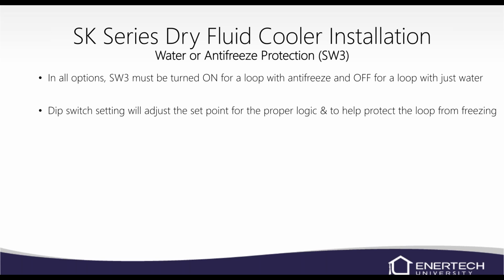Water antifreeze protection, which is switch number 3 on the dip switches. In all options, switch number 3 must be turned on for a loop with antifreeze and off for a loop with just water. So very similar to any of our other units. We're going to tell it whether you've got antifreeze in it or whether it doesn't, because that's going to give you your freeze protection settings. Obviously, it's there to protect from freezing. So if you have antifreeze in the system and you forget and leave it in the off position, then it'll just lock out prematurely rather than let it run for a little bit longer when the water temperature gets a little bit lower.